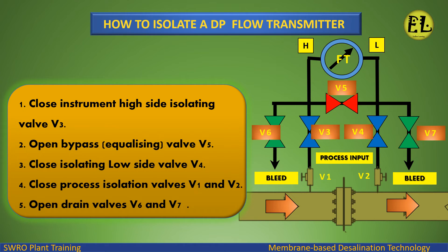Basic isolation procedure: 1. Close instrument high side isolating valve V3. 2. Open bypass equalizing valve V5. 3. Close isolating low side valve V4. 4. Close process isolation valves V1 and V2. 5. Open drain valves V6 and V7.